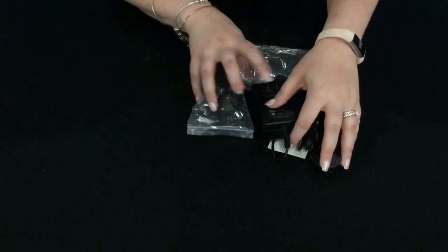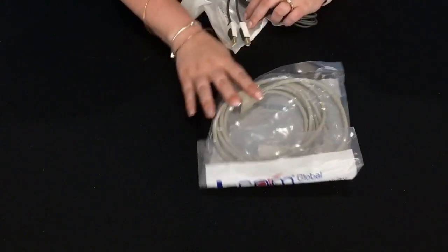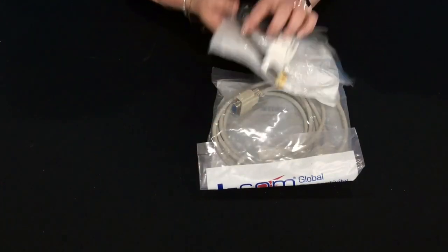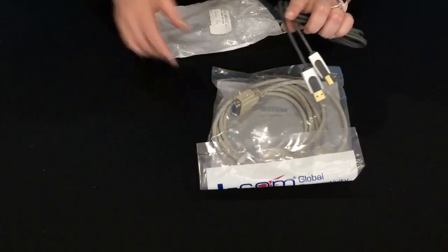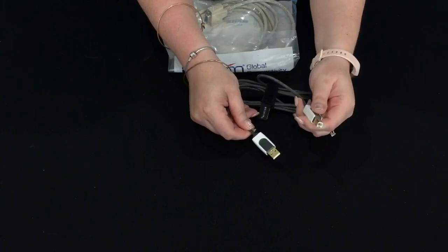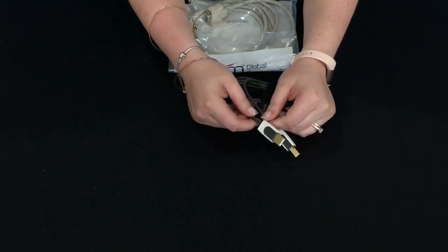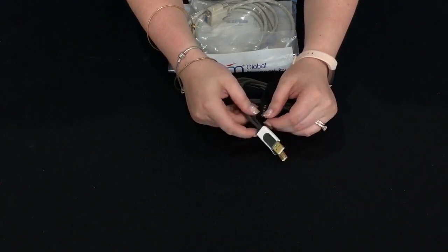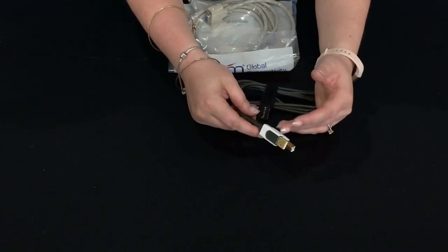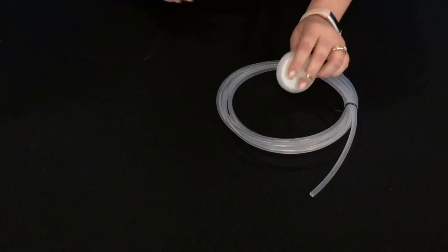In addition to powering the instrument, you will also want to be connected to it for communication. For communication, as we discussed, you have the option for RS-232, which is this cable, as well as USB serial. This will be bagged. I've taken it out of the bag to show you what the USB serial cable will look like. It has two connectors, one which will connect directly to the instrument, the other which you can connect to your computer for communicating using the software either via Windows or Mac, as well as for communication and retrieving data. As a reminder, the LI-830 and LI-850 will not have a data logger with it, so you will want to have it connected to some device while you're using it.